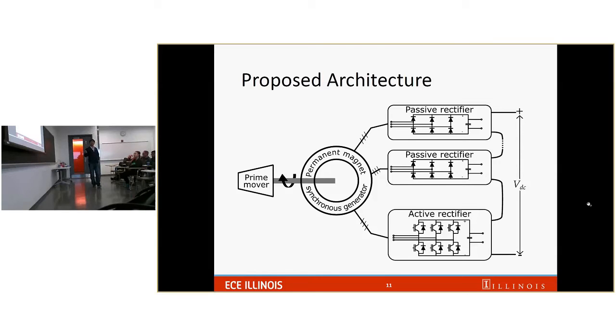The reason we pick the passive rectifier is that it is simple. It only comprises 6 diodes, and we don't need to do any control on the passive rectifier. We just feed voltage into it, and it converts AC to DC automatically. But the downside of the passive rectifier is we don't have control over the amplitude of the DC bus voltage, because the output depends on the voltage you apply on the AC side. And because we are looking at variable speed operation, the back EMF produced by the generator will depend on the operating speed. So the DC voltage on the passive rectifier will vary depending on the operating speed.